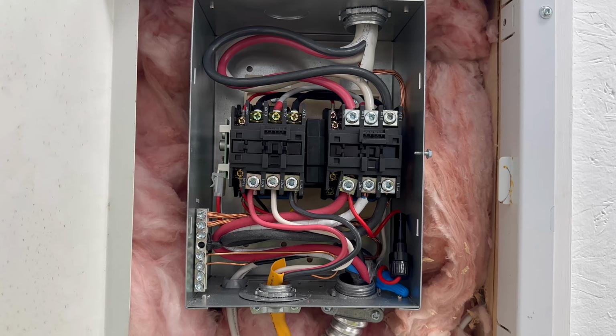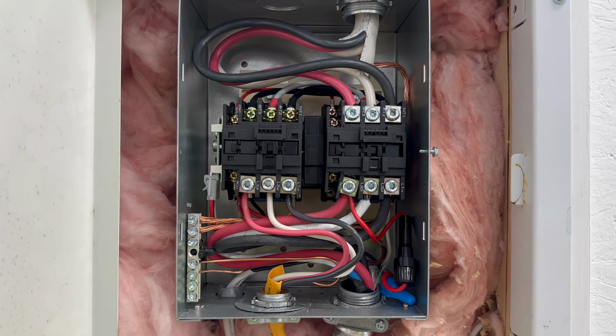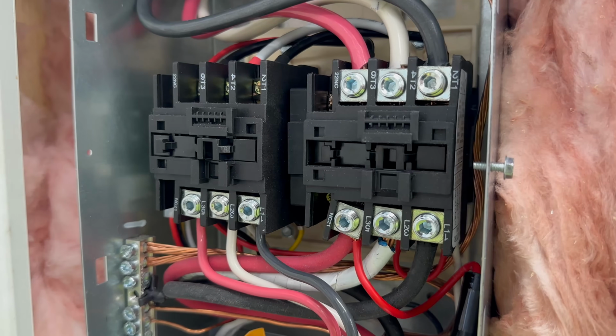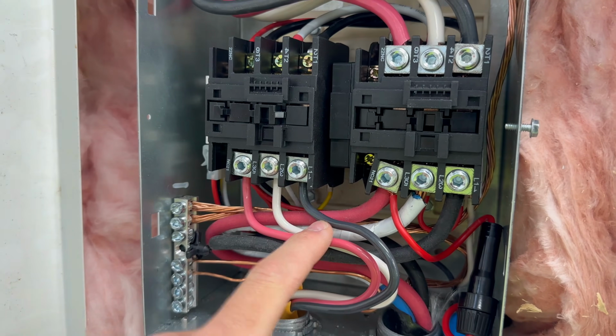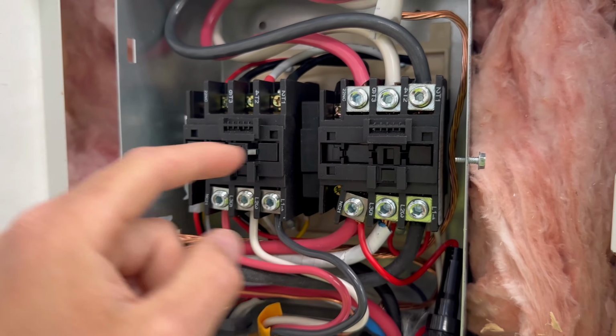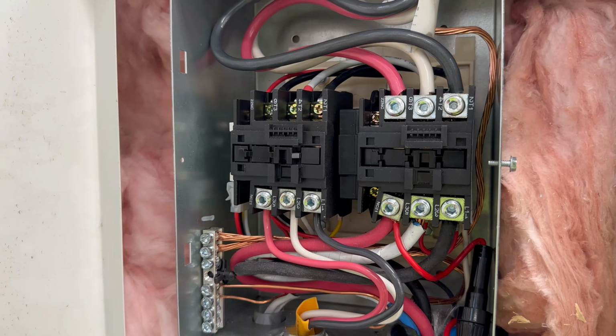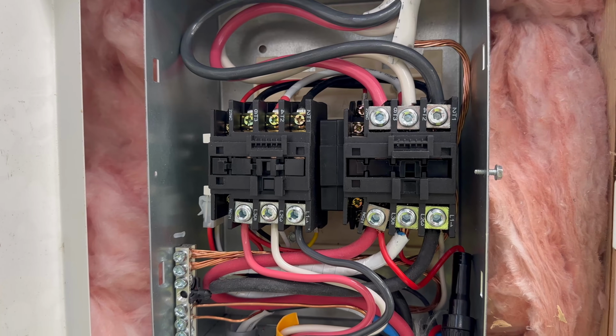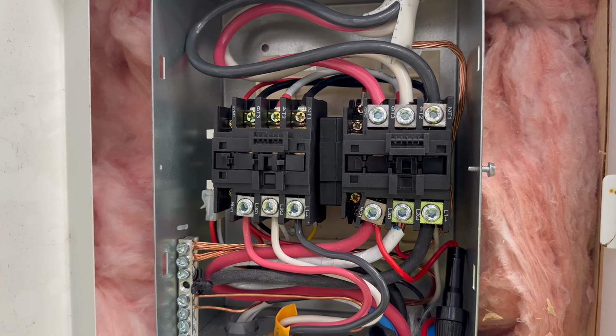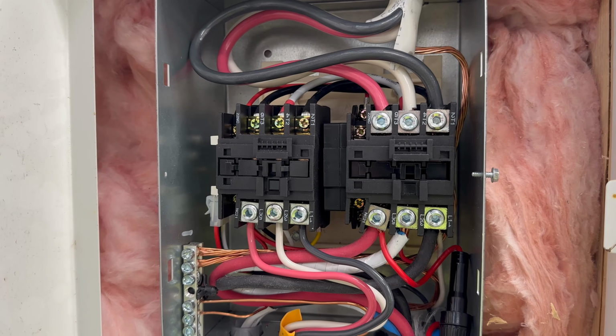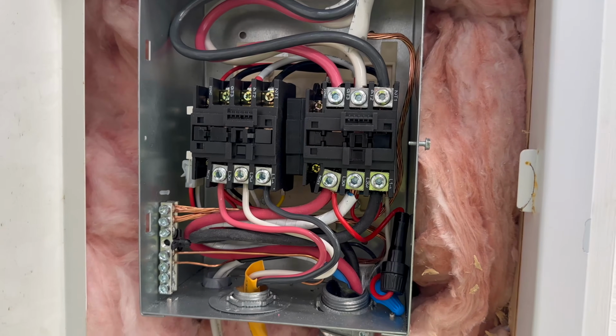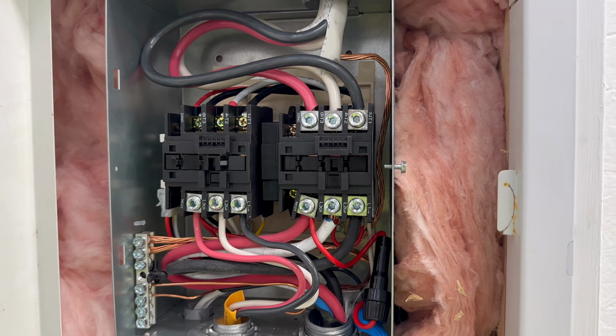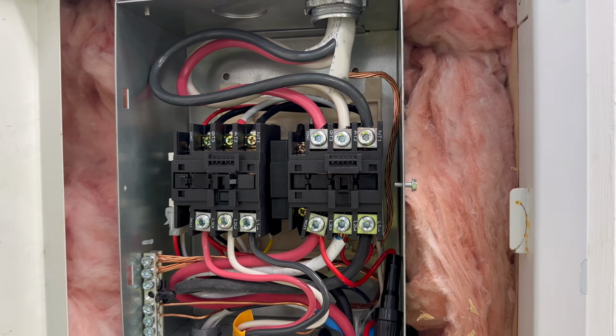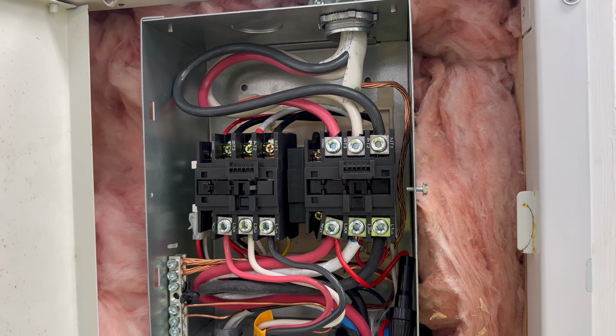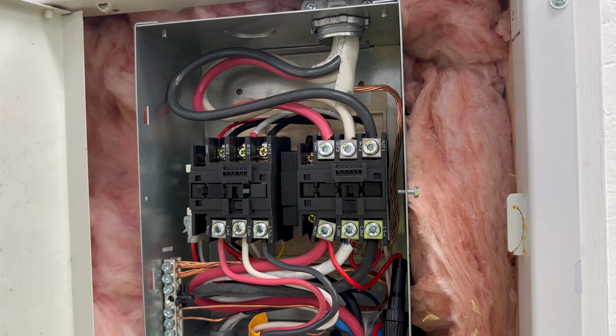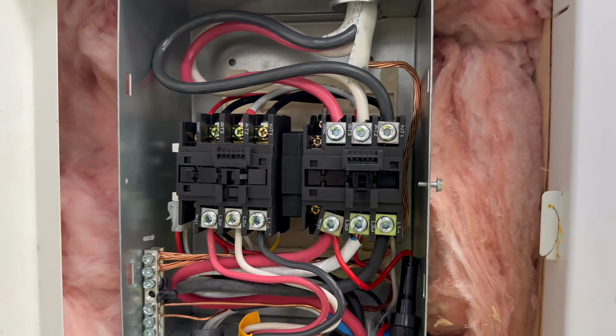Which is extremely important that this is here and in place and never closes two at once, or it could kill someone. The reason it's so important and so dangerous if you don't have it is if the generator power is on and this contact was closed in at the same time as this contact, your generator power would backfeed BC Hydro. BC Hydro uses a 25,000 volt phase to phase system, 14,400 volts phase to ground, where it is then stepped down by a transformer to 120 volt phase to neutral and 240 volt phase to phase. However, that transformer will do the exact opposite thing if you backfeed it, where it will step up 240 volts into 14,400 volts, which could kill a lineman that is not expecting there to be power, that is working on the lines trying to restore power in a power outage. That's why it is extremely important that this is installed and working correctly.